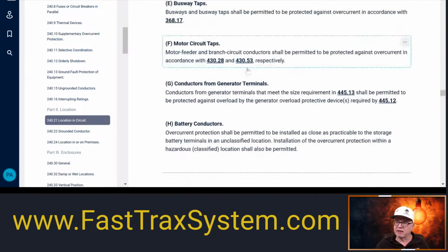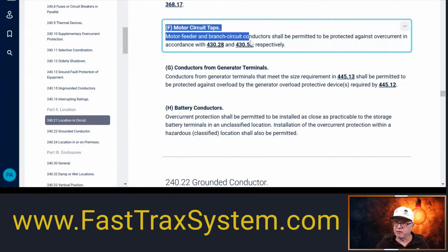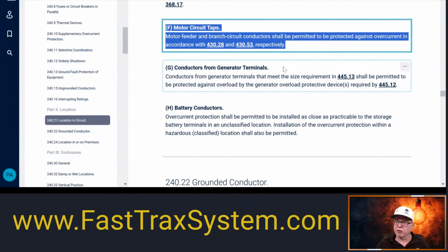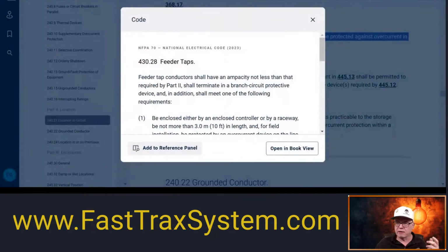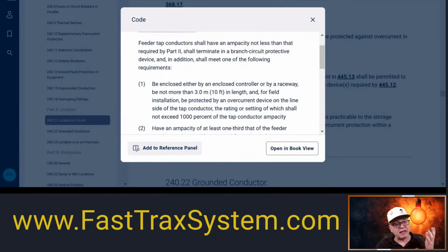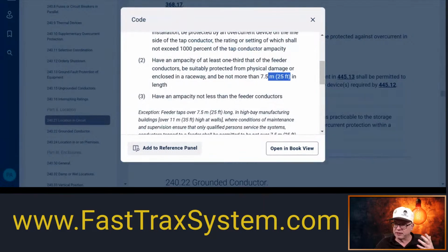We have different things for motor taps. Motor-feeder and branch-circuit conductors shall be permitted to be protected against overcurrent in accordance with 430.28 and 430.53 respectively. Again, these are tap allowances, but these are specific tap allowances for motor applications only, and you have to meet all the criteria. Ironically, this motor feeder tap application uses a lot of the same language, 10-foot length, 25-foot length, that type of thing. And then, of course, you have some exceptions.